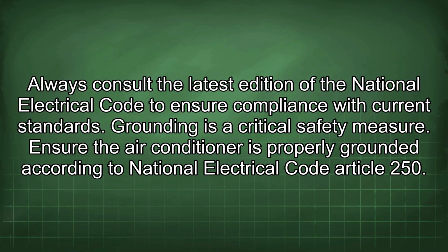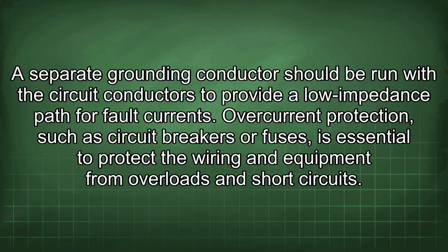Grounding is a critical safety measure. Ensure the air conditioner is properly grounded according to National Electrical Code Article 250. A separate grounding conductor should be run with the circuit conductors to provide a low impedance path for fault current.